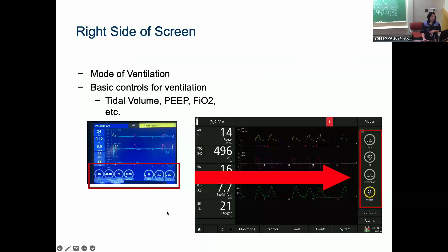You will notice this is where the flow is recorded, but also a flow pattern. And we actually have 3 flow patterns available. So previously we had the square waveform, we have a decelerating waveform, and then on the Avea, which was not really maybe talked about too much, we had a decelerating waveform that when it hit 25 or 30% of flow would drop down to 0. So it was a drop-off ledge. That was the default mode of the Avea.